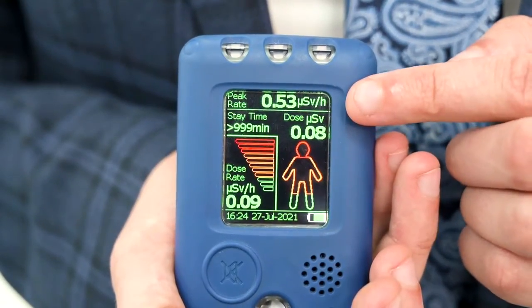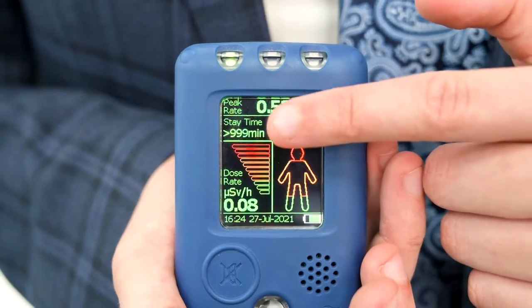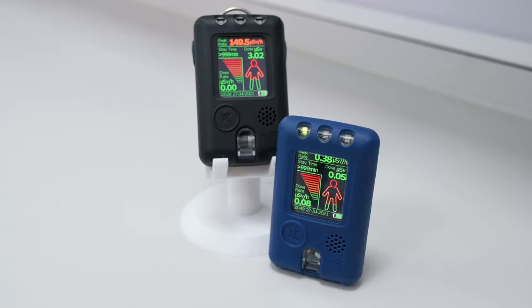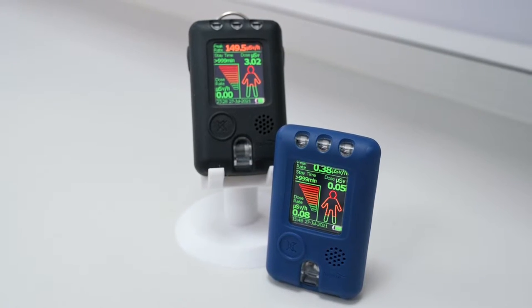On the PED's display you can see detailed information such as accumulated dose, dose rate, peak reading, and the calculated stay time. The PED measures dose rate in a range of 0 to 100 millisieverts per hour and has an energy range of 33 keV up to 3 MeV.